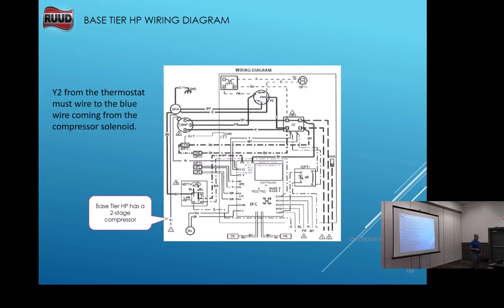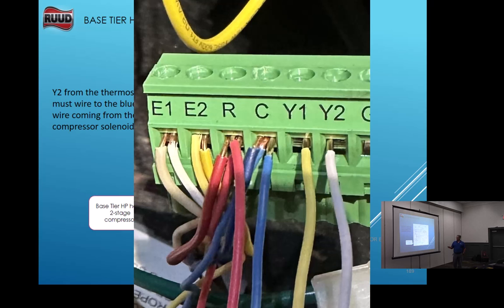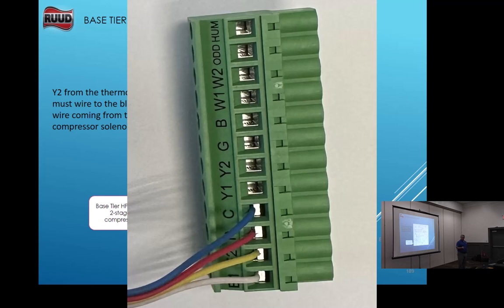Now, this is our base tier heat pump. Remember I said it's 2-stage now? You're just going to have a blue wire running from the solenoid on the side of that compressor hanging inside the cabinet. It's not connected to the board. You're just going to have Y, red and common, and O and D. Now, the thing is, there are 2 blue wires. The reversing valve wire is a light blue wire, and the second stage solenoid wire is a dark blue wire. And of course, they put all of these in a bundle together, and it doesn't really tell you anywhere, so you have to trace the wire out to figure it out.